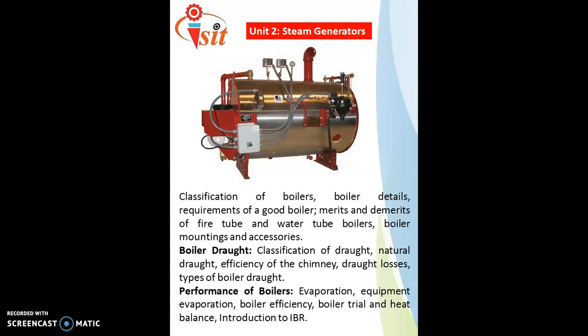There are two types of boilers: fire tube boiler and water tube boiler. In a fire tube boiler, the fire is continuously inside and it gets surrounded by water. But in the case of a water tube boiler, water is circulated through the tubes and it gets surrounded by fire. For ease of operation and safety purposes, we generally use mountings and accessories. The mountings are the essential devices — they include safety valves, fittings, water level indicators, etc. The accessories improve the performance of the steam generator and include the economizer, superheater, air preheater, etc.